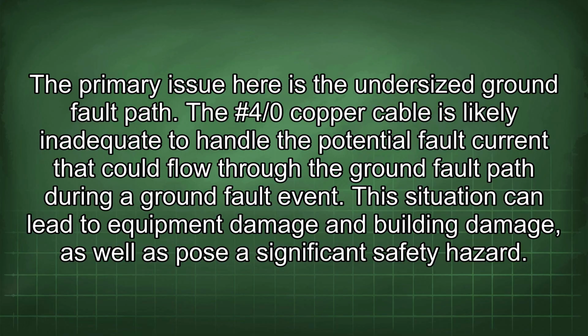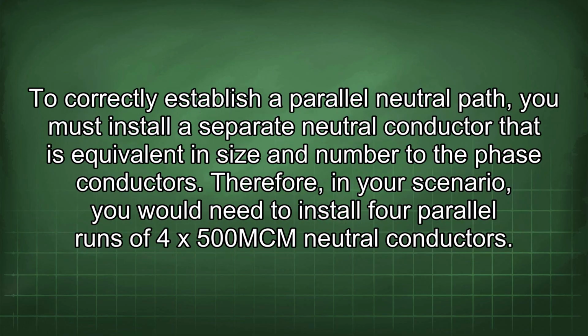The primary issue here is the undersized ground fault path. The #4/0 copper cable is likely inadequate to handle the potential fault current that could flow through the ground fault path during a ground fault event. This situation can lead to equipment damage and building damage, as well as pose a significant safety hazard. To correctly establish a parallel neutral path, you must install a separate neutral conductor that is equivalent in size and number to the phase conductors. Therefore, in your scenario, you would need to install 4 parallel runs of 4x500 MCM neutral conductors.